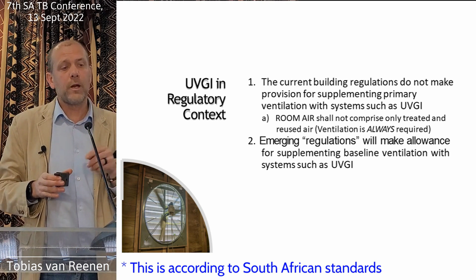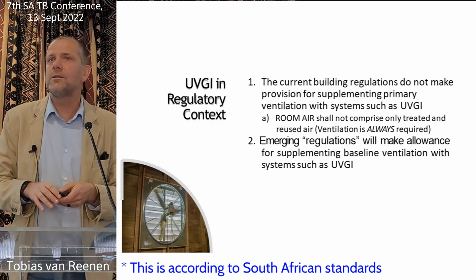However, currently, to meet the regulation requirements, you have to do that all with ventilation. Anything you do with UV is over and above. The emerging regulations now will make allowance for a supplementary baseline ventilation, a minimum amount of the air changes must be mechanically ventilated, but for instance 2 air changes, and then you can make up the rest, up to 10 air changes or whatever, with UVGI. Is that clear? Okay. So we're trying to be progressive with the regulations to allow for these kinds of technologies and emerging systems. And you're going to see this slide a lot.